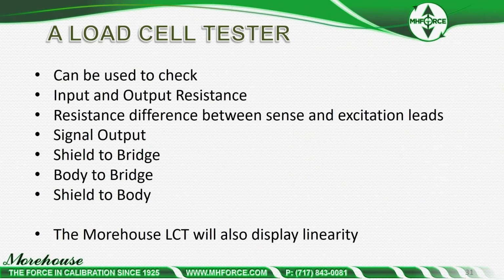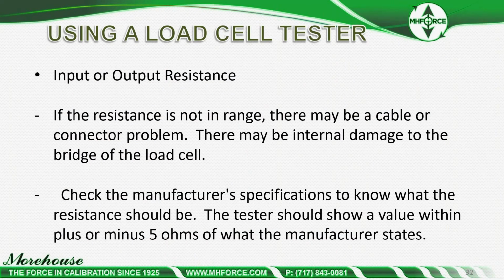So a load cell tester, what can you use it for? As I said, you're going to be primarily concerned with input and output resistance, resistance difference between sense and excitation leads, signal output, and then these other ones, shield to bridge, and shield to body. These are all things that can help diagnose problems. Important to note that if you want to know linearity, the Morehouse load cell tester will also display linearity. It's a separate mode. You can go to it and start applying capacity and see how linear the device is. But what we're really concerned with is input or output resistance.